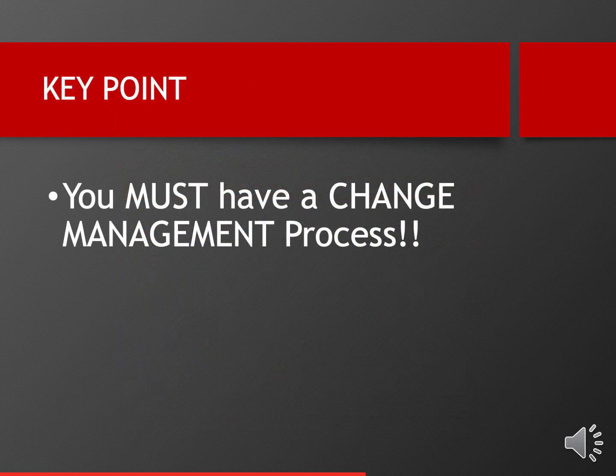Now this slide relates to our previous discussion that we had about incident energy going from 2.9 to 66 calories. And the point here is that you have to have some kind of a change management process to alert the engineers who did the study when components of the system have changed. And that can happen because you've added or subtracted load, and in particular larger loads, motors of maybe 20 horsepower or more, transformers of say 30 kVA or more. If you add or subtract those loads, either one, we need to know that from the engineering side of the house.